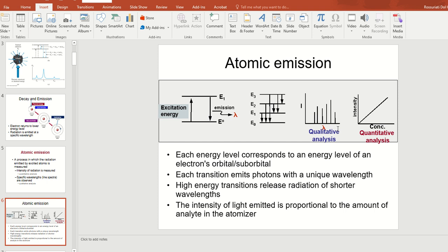to get some idea of what kind of element this wavelength actually represents. Is it aluminium? Is it iron? Basically, the instrument has a database, a collection: for aluminium, the wavelength where the maximum intensity is observed; for iron, the wavelength where the maximum intensity was observed.